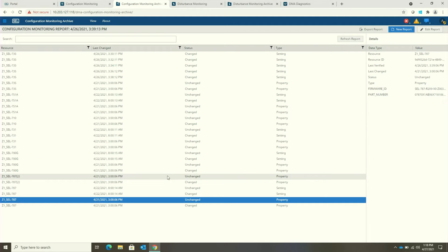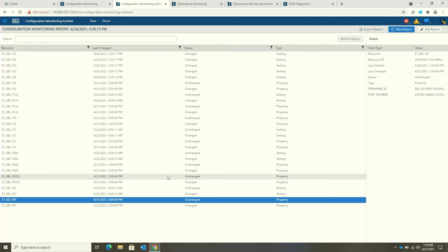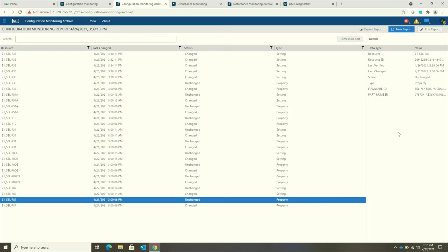Once in the archive, users will be able to see a report of the information collected for these devices, identify when we last communicated with a device, and understand if the settings or properties information has changed or if it's remained the same. The properties information includes the part number and firmware version information. One key advantage of our solution is that when we collect settings information back from these IEDs, we are actually collecting the set.txt files that are compatible to be imported into your SCL configuration management software.